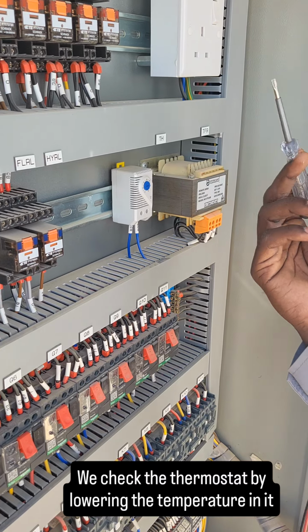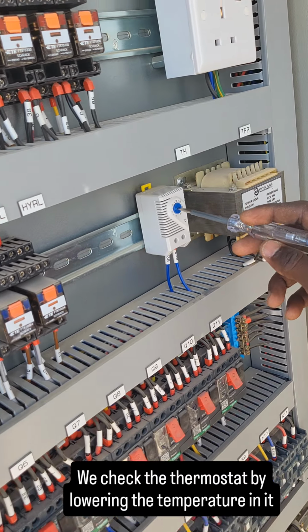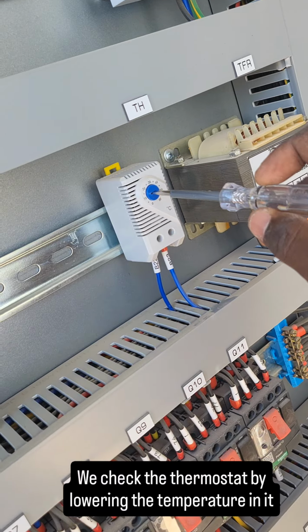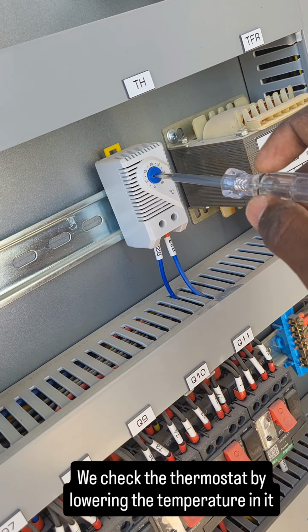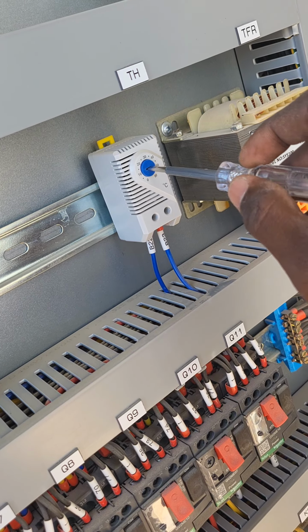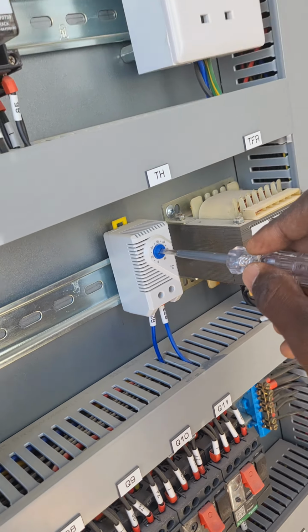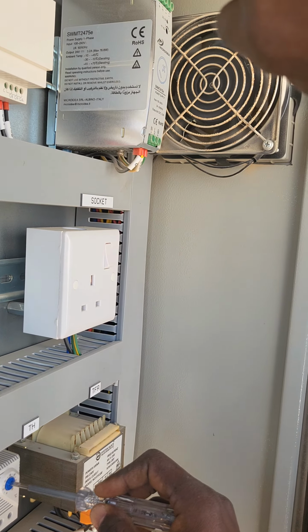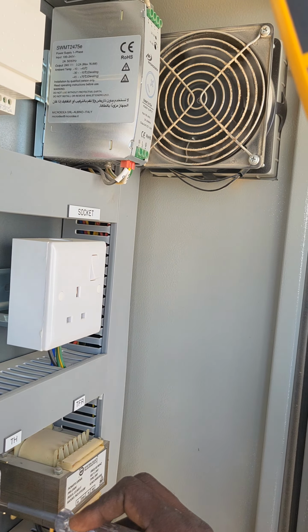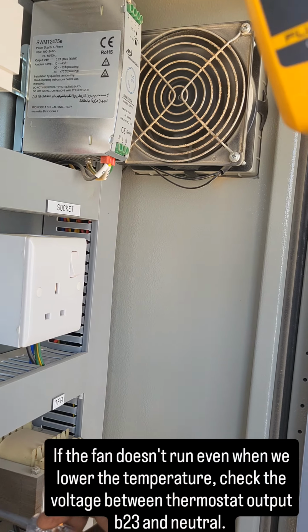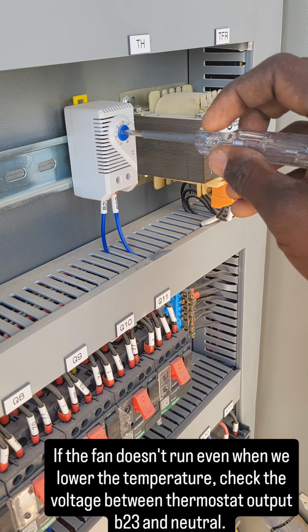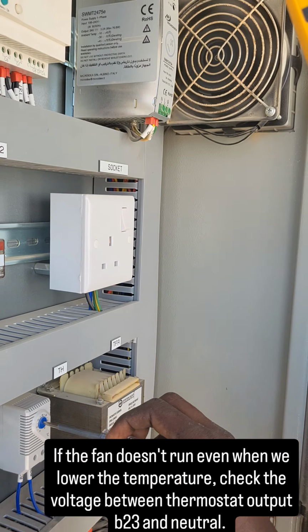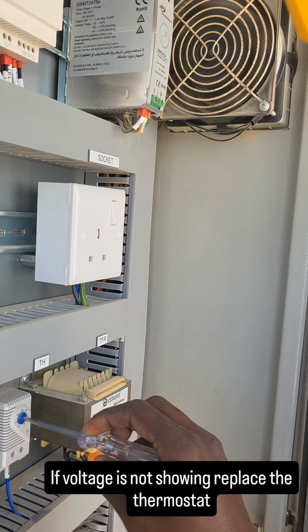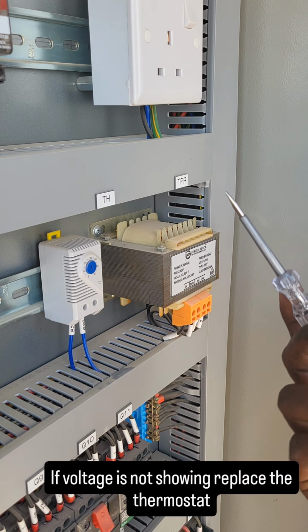Now we can check whether the thermostat is good or not by decreasing the set temperature by rotating the knob. Now see, if we rotate or decrease the temperature on the thermostat, the fan should run. Now let's check. See, the fan is running. As we decrease the temperature on the thermostat, the fan is running, so the thermostat is good. In this troubleshooting, the electrical circuit is good.